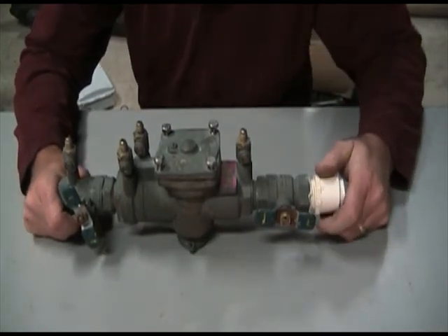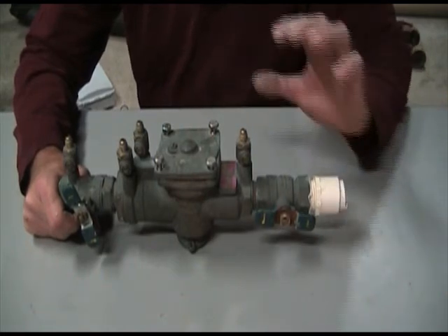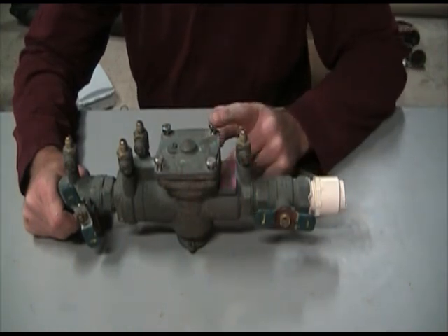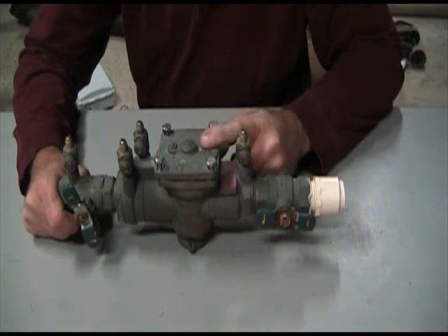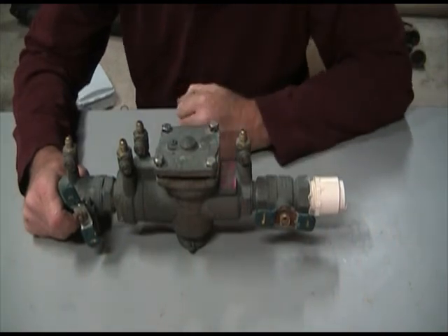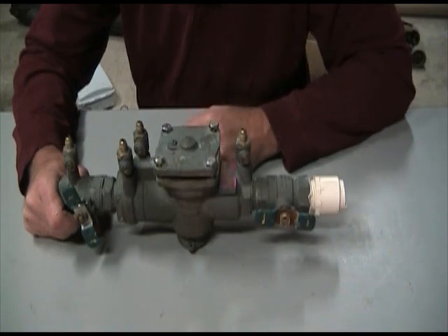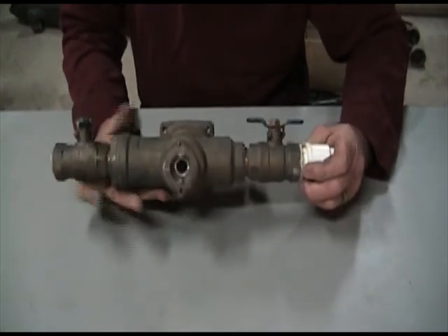Now if you have a sprinkler system where you have sprinkler heads that are above the water source, that are higher, you would need to use one of these. Okay? And they always use a dual check or a reduced pressure backflow preventer if they ever put one indoors. Where I'm at, you always have to use one of these if the sprinkler head is above the water source, or you put one indoors. If you put it indoors, this has a drain on the bottom. You have to be able to take this to a floor drain in the house.